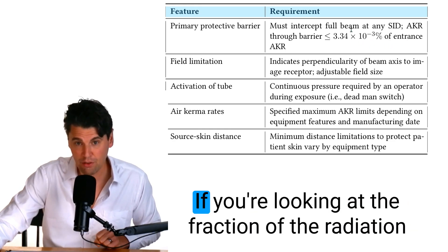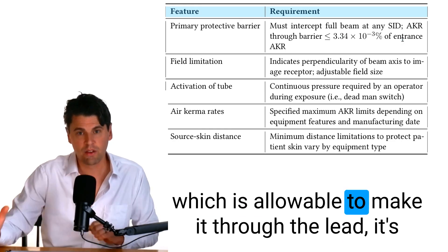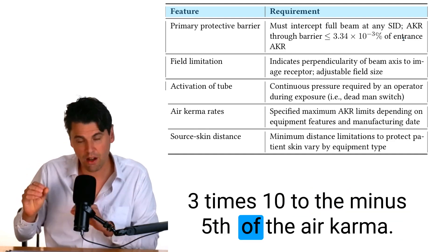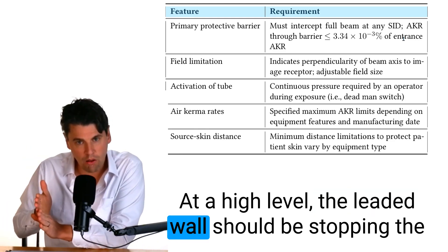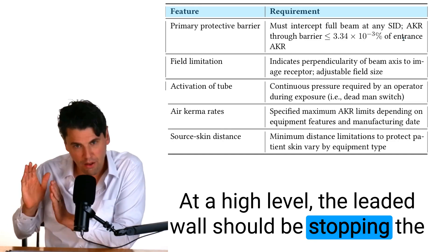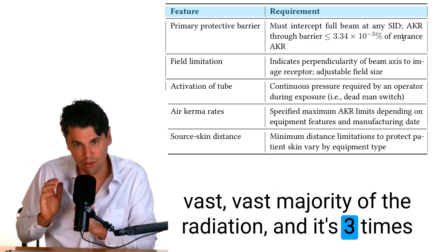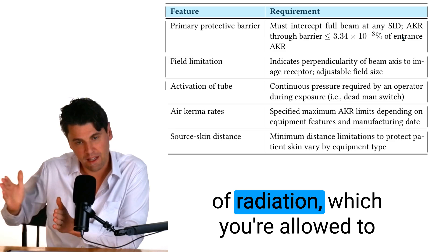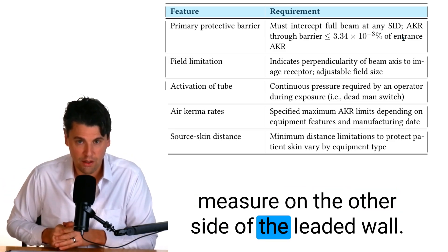If you're looking at the fraction of the radiation which is allowable to make it through the lead it's 3×10^-5 of the air kerma. At a high level the leaded wall should be stopping the vast vast majority of the radiation and it's 3×10^-3 percent of radiation which you're allowed to measure on the other side of the leaded wall.